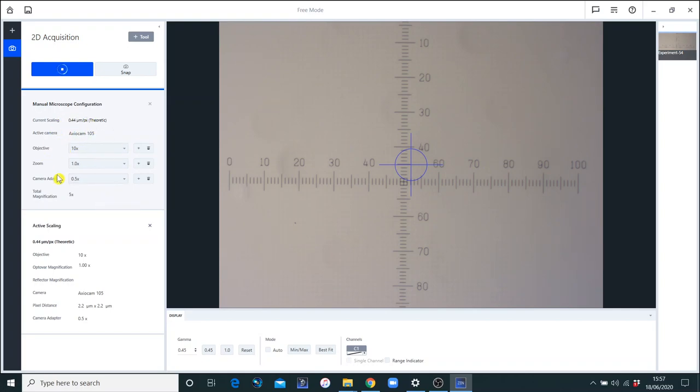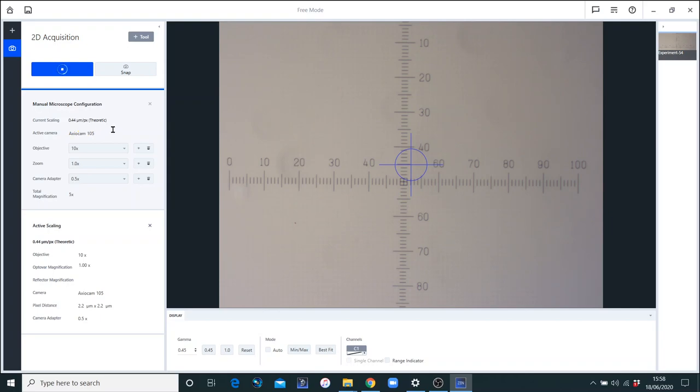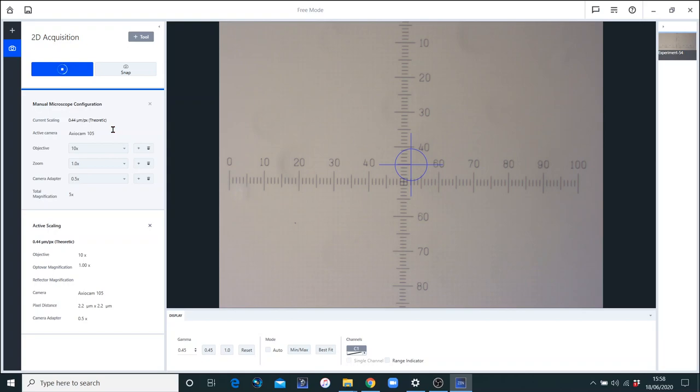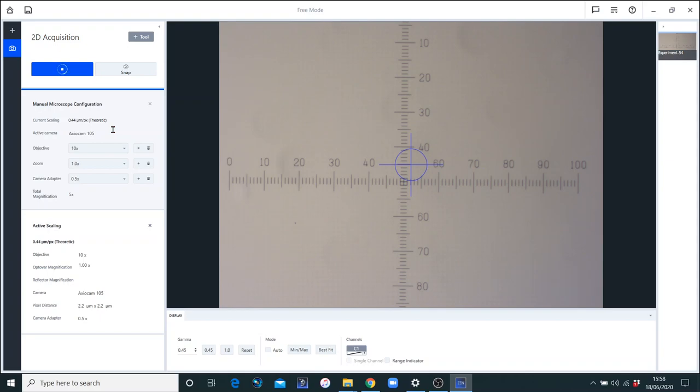Camera, you can't change that. That's part of the configuration of the software. So you can see here that we've got a calculated value of 0.44 microns per pixel, or about 0.5 microns. So what that says is that each pixel is half a micron wide, and by doing that, we can work out the size of the picture. Now, theoretical calibrations are theoretical, so they are not measured. They are prone to error and they're prone to probably between one and five percent error.